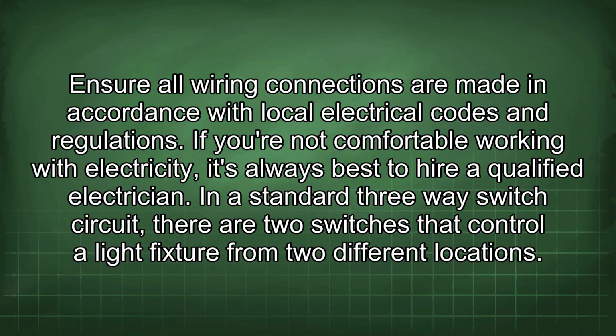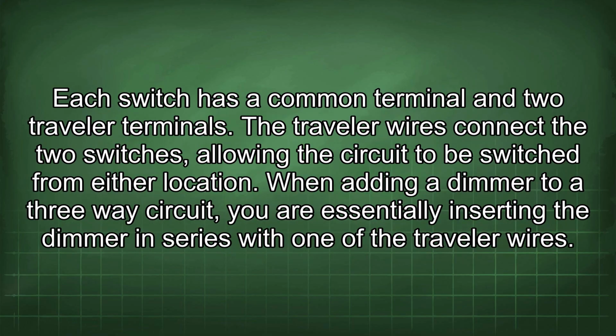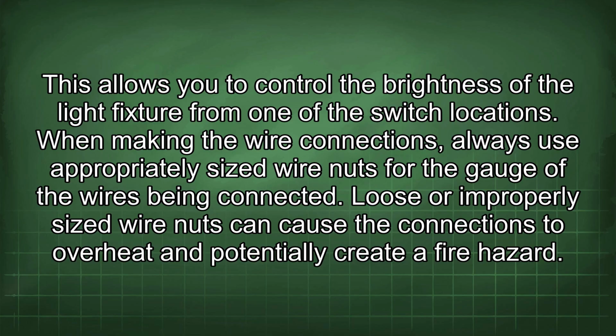In a standard three-way switch circuit, there are two switches that control a light fixture from two different locations. Each switch has a common terminal and two traveler terminals. The traveler wires connect the two switches, allowing the circuit to be switched from either location. When adding a dimmer to a three-way circuit, you are essentially inserting the dimmer in series with one of the traveler wires. This allows you to control the brightness of the light fixture from one of the switch locations.